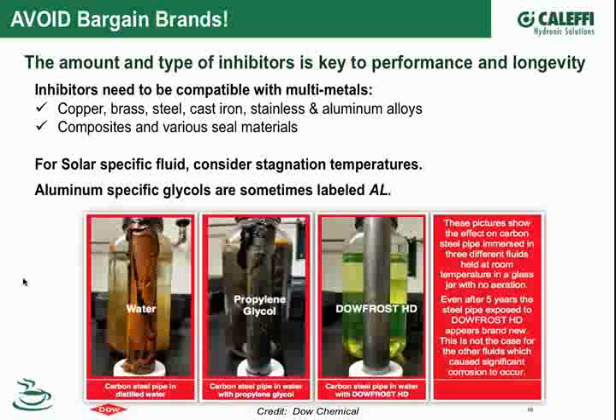It's a good point, not all fluids are. It's difficult, actually it's impossible to have a fluid that provides 100% protection to all different kinds of metals. When you're designing a system, fewer metals is a much better option than having multiple metals. When you start mixing aluminum with stainless, carbon steel, and copper, it's almost impossible to protect all those metals from corroding. Something's got to give, so you're better served to minimize the number of different metals in your system when at all possible.